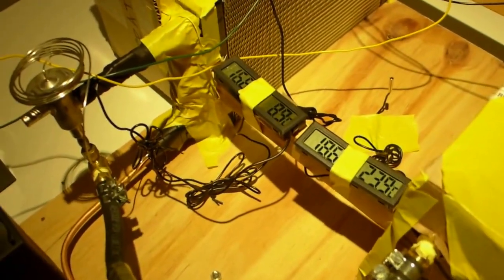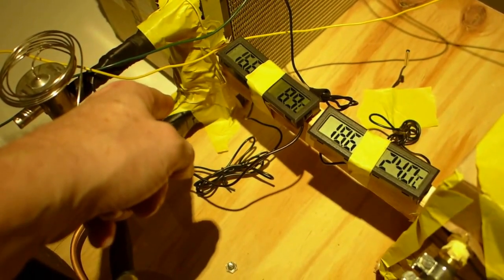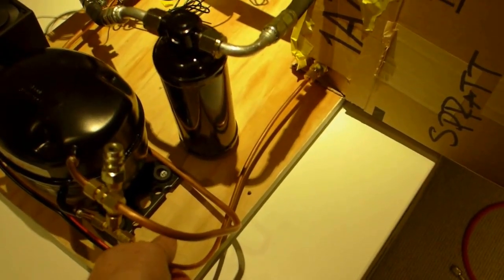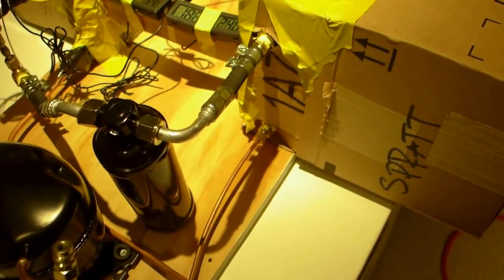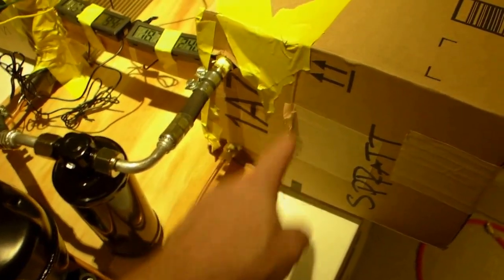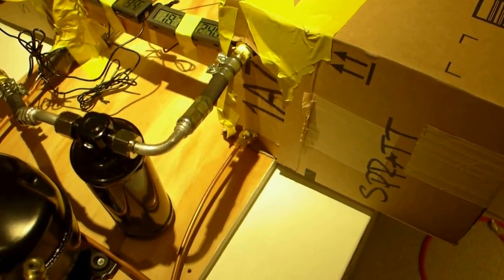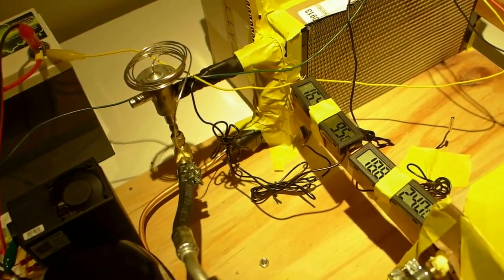So it's cooling at five and a half degrees C. So you feel the temperature here, you feel it there. It's just 18 degrees blown out of there. And then these two. This is nine degrees is the temperature of the evaporator going up on the input side. And then coming out at 16 degrees coming back to the compressor. And I've previously measured the temperatures coming out of the compressor and into the condenser. And I'm getting about a 20 degrees C temperature drop across this unit here. It's about 50 degrees C coming in and about 30 coming out going into this. And then it goes through the expansion valve. Temperature drops obviously a lot and then it goes in.